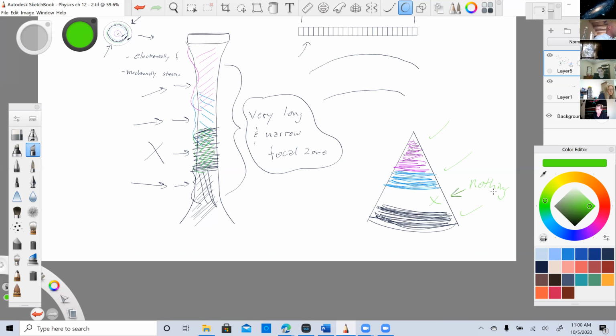Let me go back to the beginning of this chapter because we have that list of shape and number of active elements. How many? The book doesn't give us a number of elements that are typical for this transducer, but we do know the shape, that they are ring shaped. Automatic redirection of sound beams to create an image.